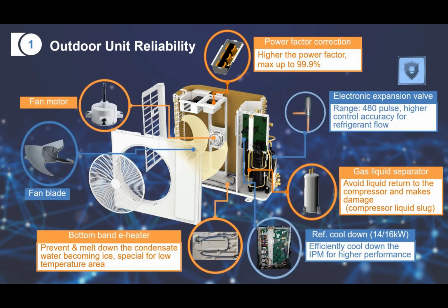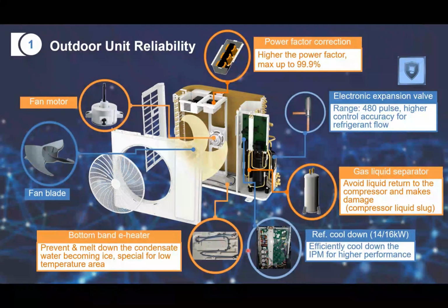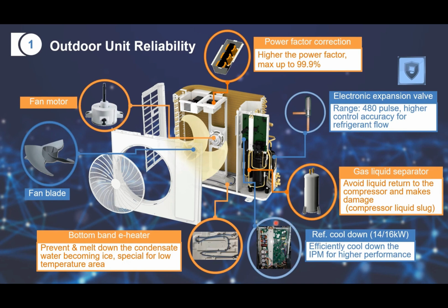For the outdoor unit reliability, we also developed and improved the inside components. First, for a higher power factor, we have this reactor put here. Also, the whole series applies the EXV for metering. As you know, EXV also means high accuracy refrigerant control. And we have the gas liquid separator to avoid compressor liquid slugging. For 16 and 14 kilowatt, the outdoor unit PCB applies refrigerant cooling, just like this. This also improves the compressor and even the system efficiency.